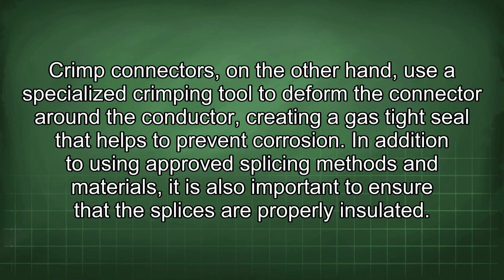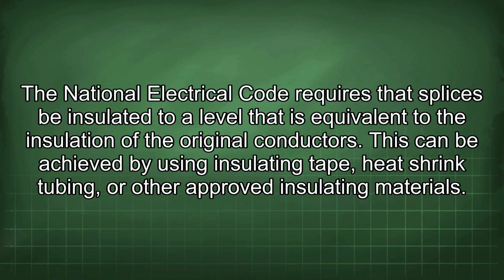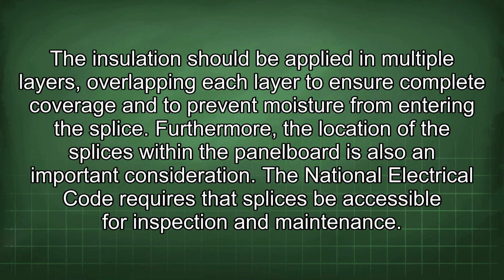In addition to using approved splicing methods and materials, it is also important to ensure that the splices are properly insulated. The National Electrical Code requires that splices be insulated to a level that is equivalent to the insulation of the original conductors. This can be achieved by using insulating tape, heat shrink tubing, or other approved insulating materials. The insulation should be applied in multiple layers, overlapping each layer to ensure complete coverage and to prevent moisture from entering the splice.